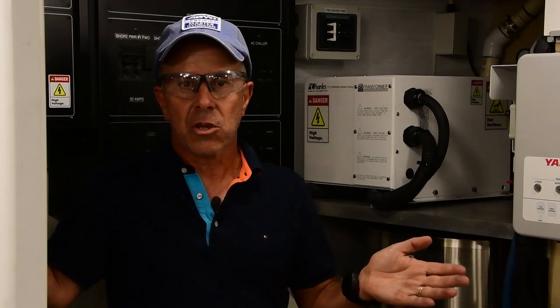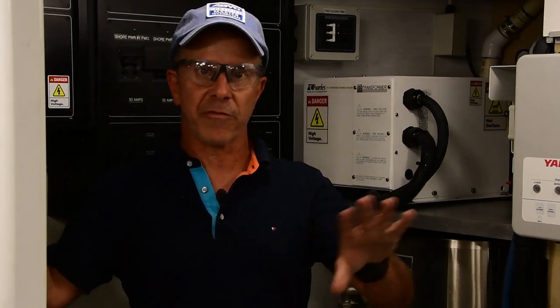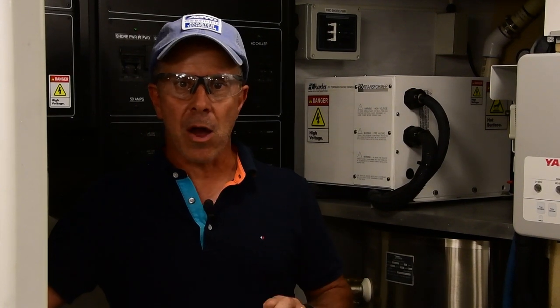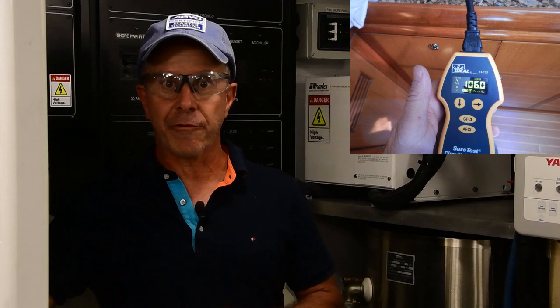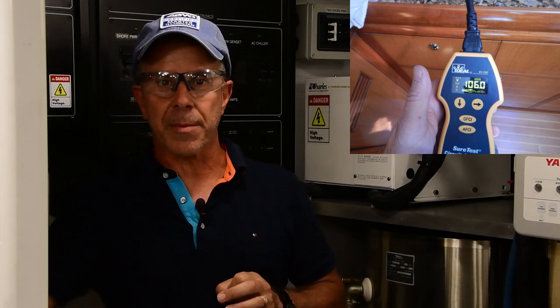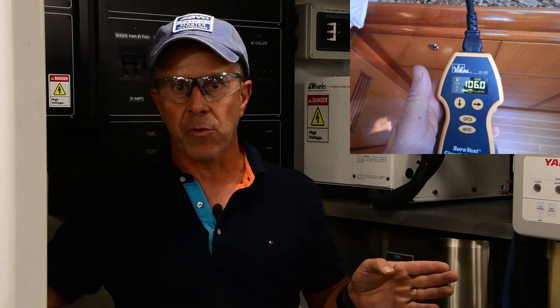Now, in my opinion, a transformer should never be installed aboard a split phase boat that is not the boosting variety. Why do I say that? Well, obviously you want that benefit of being able to boost the voltage, but if you install a transformer that doesn't have the boosting feature on a split phase boat, again 240, 120, when you plug that boat into 208, that transformer is going to convert that to 208 and 104. So that means anything that's being plugged into a conventional outlet inside the boat will now, instead of getting 120 volts, get 104 volts or less. Whatever the voltage that's coming into the boat, it will be cut in half for that 120 volt circuit.